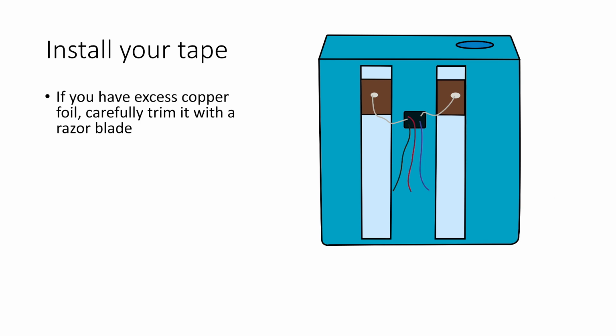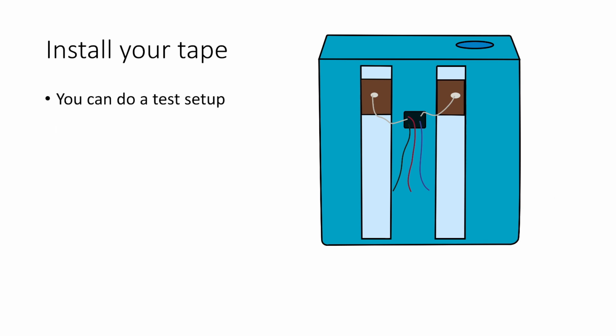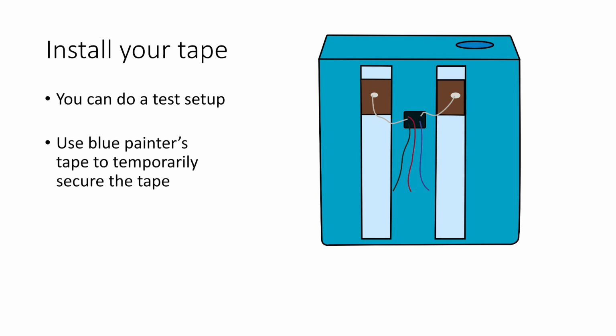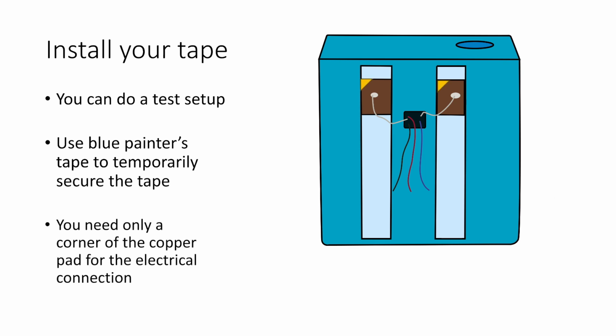Peel off the back of the sensor and stick it to a clean surface on the tank. If you would prefer, you can stick the tape to the wall of the tank before peeling the backing off with blue painter's tape to find the location and do your testing, but this is not necessary. You can tack the copper foil on with just a corner to get the electrical connection you need for testing.